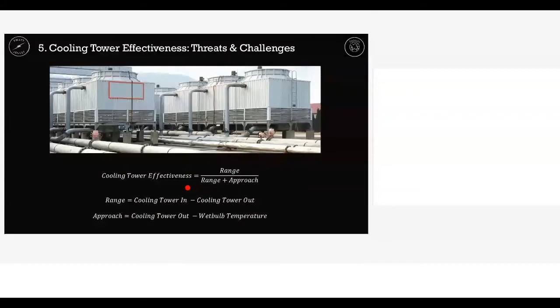So in the cooling tower, a little bit into the process part, deviating from the data. If you don't know what the cooling tower approach is, if you don't have an IoT or a BMS platform to fetch the data and show it to you in real time, the plant room will still operate. Whether the cooling tower approach is 2 degrees Fahrenheit or 12 degrees Fahrenheit, your AC plant room will still operate. But at 2 degrees Fahrenheit it will consume 100 units of energy, and at 12 degrees Fahrenheit it will consume 500 units of energy. But nobody will know - you'll only find out when you get the electricity bill.